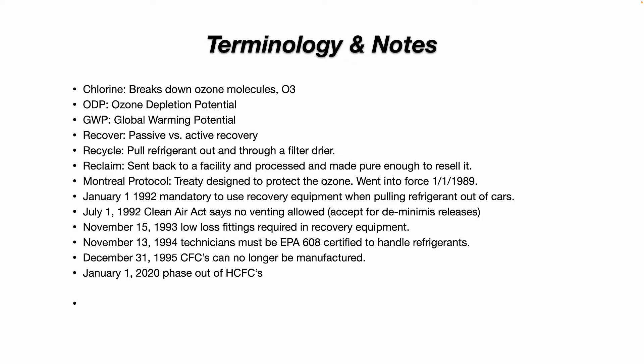January 1, 1992, it became mandatory to use recovery equipment when pulling refrigerant out of cars. July 1, 1992, the Clean Air Act stated no venting allowed except for de minimis releases. A de minimis release is, for example, when you hook up your gauges or hoses to an appliance and get that little squirt of refrigerant — that's a de minimis release.